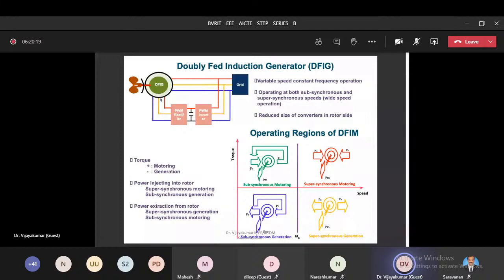In supersynchronous generation, we take power output from the stator as well as the slip power output from the rotor. So you take the power output from the rotor and inject it back to the grid through the back-to-back converters.